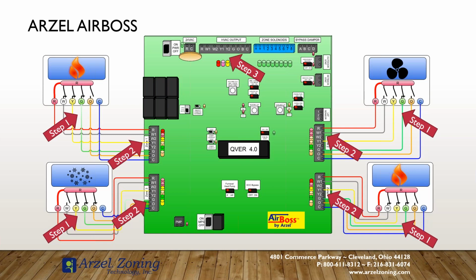The panel is going to have several diagnostic lights on it. It might be first and second stage heating, LAT, might be compressor lockouts. So the panel does have indicators to tell you that it's got something disabled.